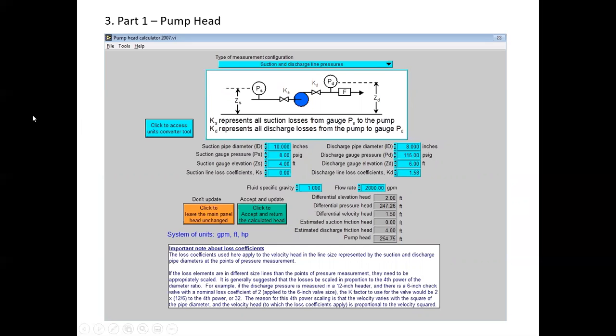So what you can do is calculate the K based on that 4-foot loss at the flow rate, or you can just put all the information into the head calculator, and you can monkey with this discharge coefficient until it gives a 4-foot frictional head loss on the discharge side of the pipe. So either way, I think for a different situation we actually calculated this same K before.